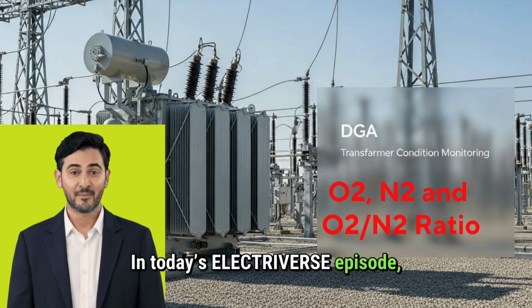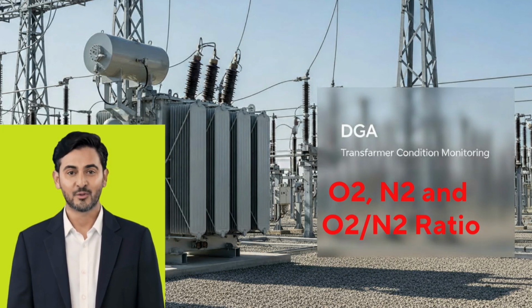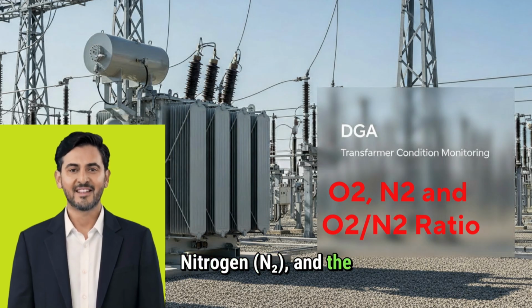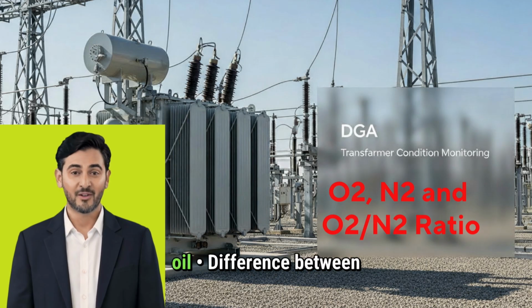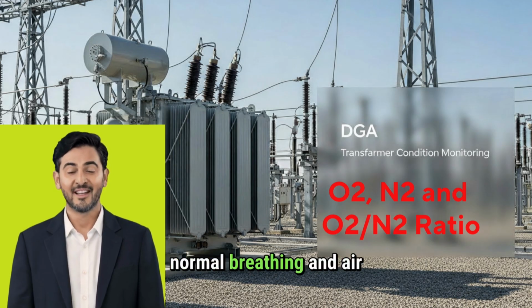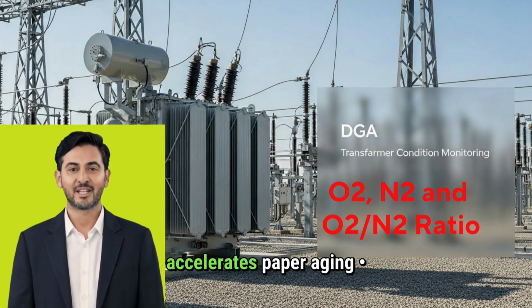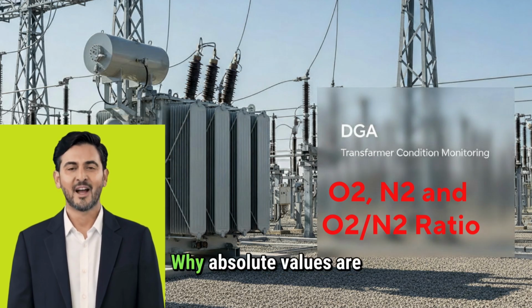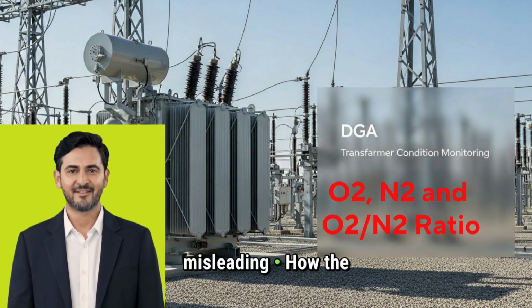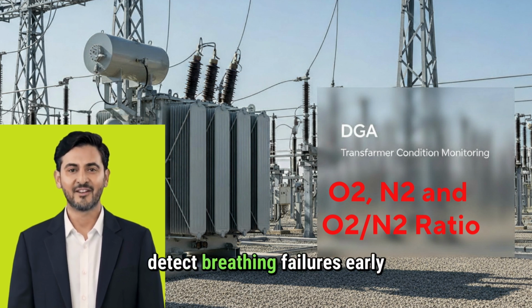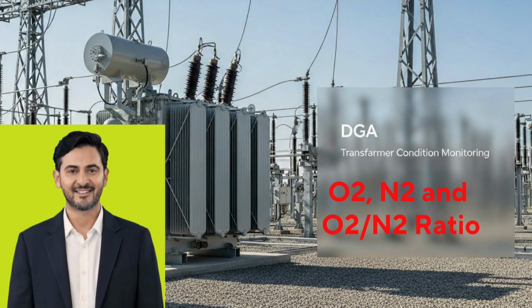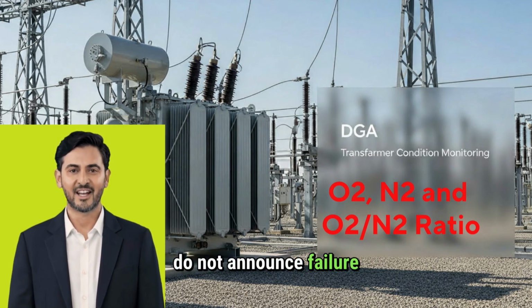In today's Electriverse episode, we decode oxygen, O2, nitrogen, N2, and the O2-N2 ratio: why O2 and N2 are always present in oil, the difference between normal breathing and air ingress, how O2 accelerates paper aging, why absolute values are misleading, how the O2-N2 ratio reveals leaks and sealing problems, and how senior engineers detect breathing failures early. Stay till the end, because O2 and N2 do not announce failure, they silently prepare it.